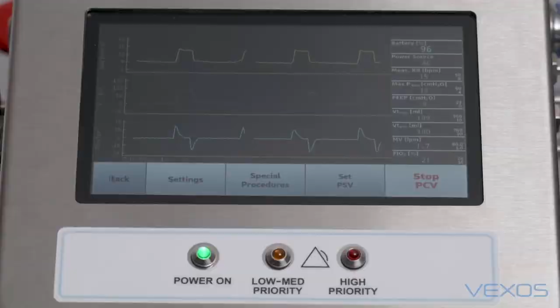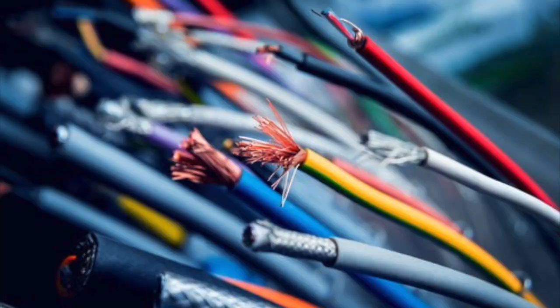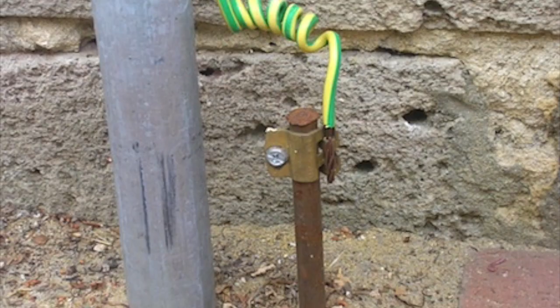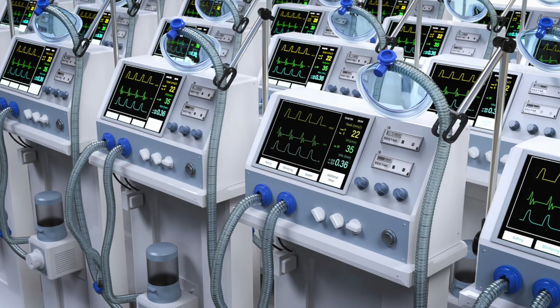During the normal functioning of most electrical equipment, some amount of current flows along the earth conductor towards the earth. Known as leakage current, it can cause harm to humans who come in contact with this current. With medical devices such as ventilators placed in physical contact with a patient's body, this becomes a serious problem. Therefore, for medical equipment like ventilators, very low leakage current is an important specification that they need to comply with.